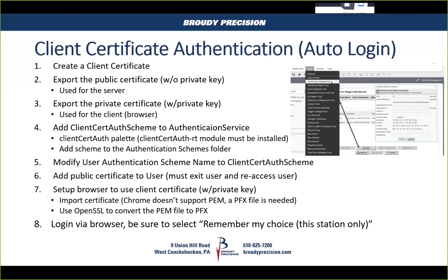So you have to use a conversion tool. OpenSSL is what's recommended and can be used to do that conversion. It's not the simplest form. We were able to get through it and get it set up, but it's not just a matter of copying that file into Chrome, since it doesn't use the format that we're used to using in Niagara.